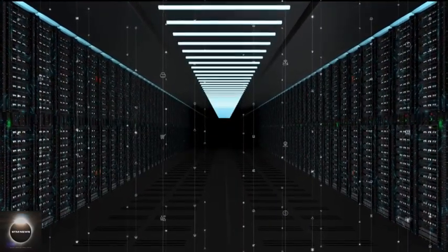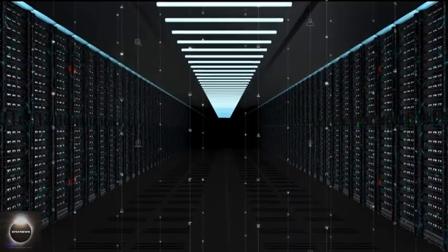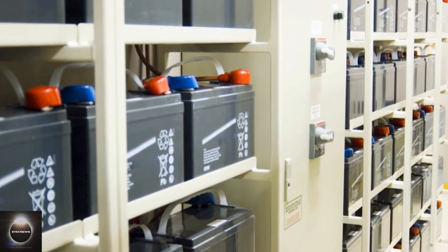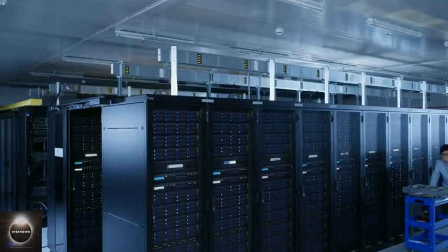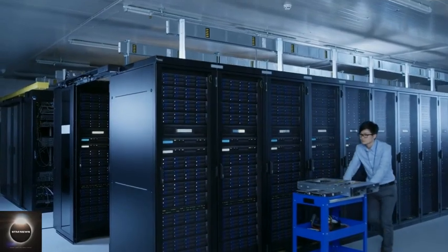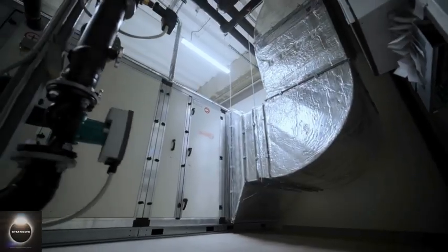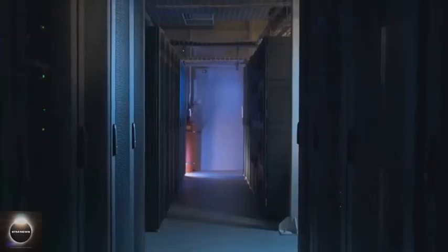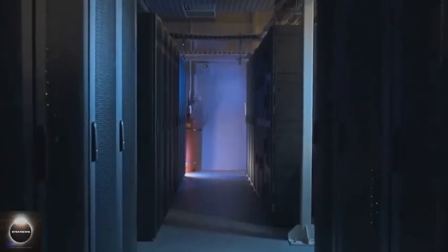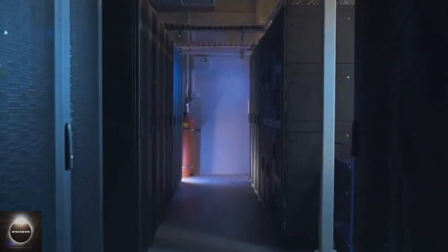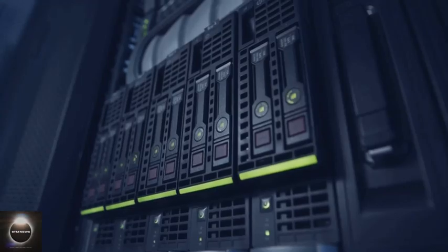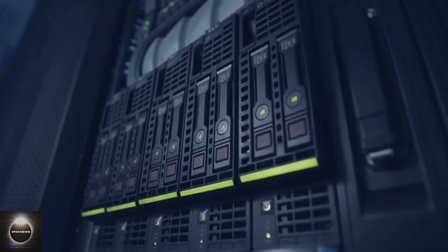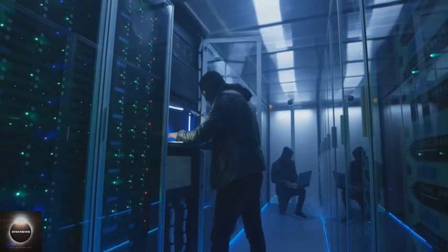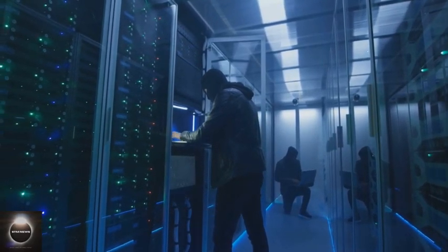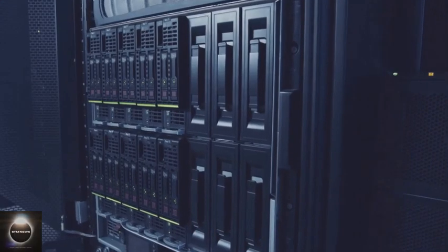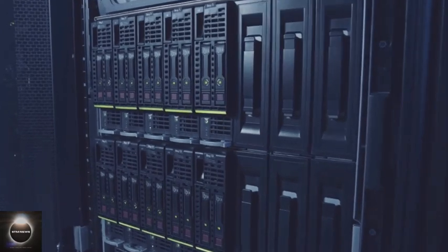Removing server heat requires industrial-scale engineering, most commonly using air. CRAC units use a direct refrigeration cycle, compressors and refrigerant to cool air. CRAH units use chilled water, much like a radiator exchanging heat from air to water. Central plants host multiple chillers running a vapor compression cycle. They deliver 45 to 55 degree, or 7 to 13 degree Celsius, water through insulated loops to CRAHs near data halls. Warm room air passes over cold coils and returns cooled air to the IT space. Direct expansion systems cool air in-unit and reject heat outdoors. Simpler, better for smaller rooms. Technicians manage refrigerant, pressures, and precise controls to keep systems in harmony.